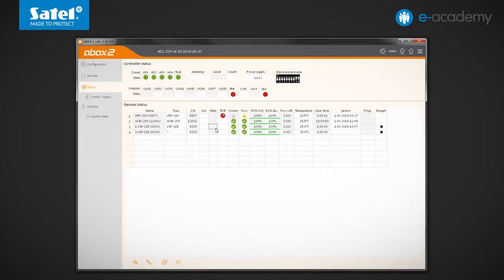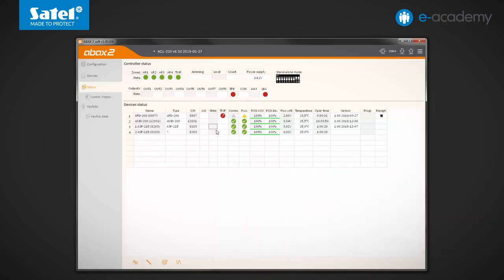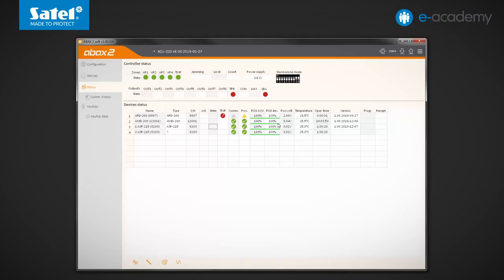In the device's status table, the radio signal level indicators can also be seen. The first of them, or RSSI ACU, informs you about the level of signal received from a given device by the controller. The second indicator informs you about the level of signal received by the device from the controller. These indications are presented as a percentage or in units of power.